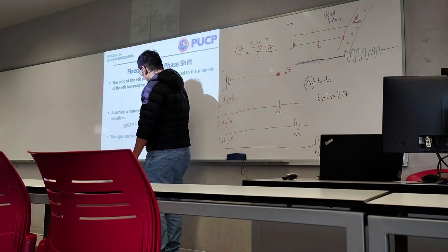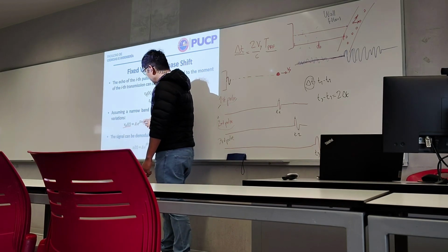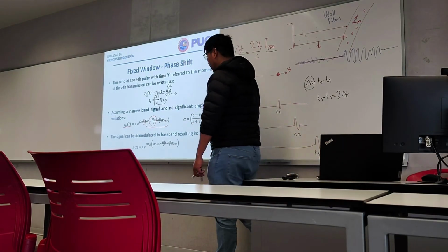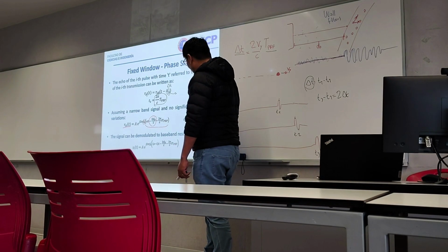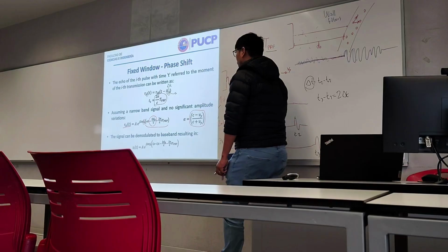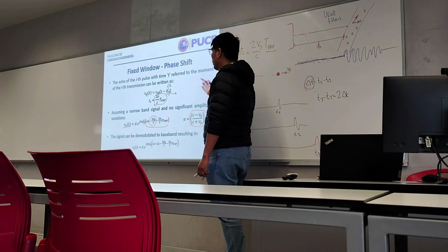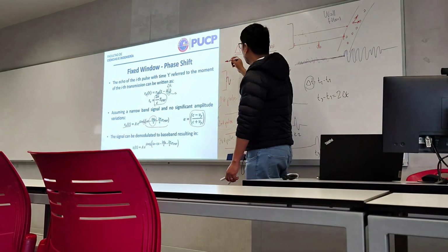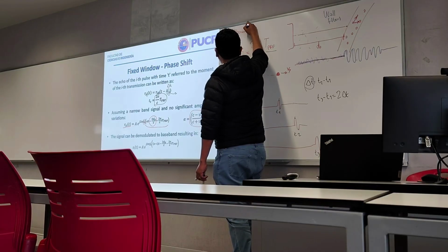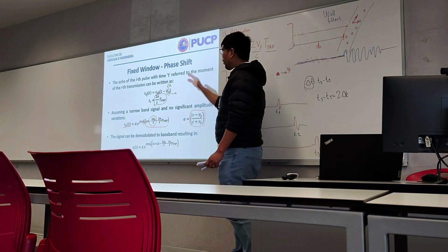The frequency of the signal that is received by Doppler is not the F0, the original F0 that was transmitted. It will be changed. And how much is it changed? How much is given by this factor, this factor alpha. In acoustics, alpha is also a common variable used for attenuation. I think we didn't mention this property, but this alpha here is not related to attenuation.